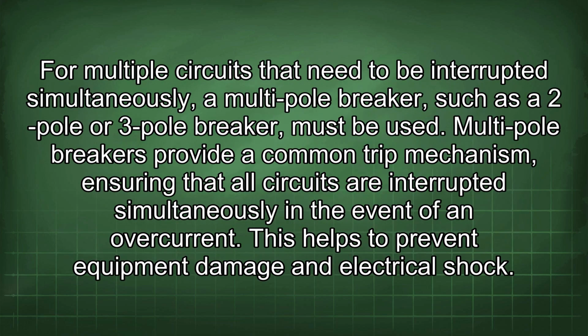For multiple circuits that need to be interrupted simultaneously, a multi-pole breaker, such as a two-pole or three-pole breaker, must be used. Multi-pole breakers provide a common trip mechanism, ensuring that all circuits are interrupted simultaneously in the event of an overcurrent. This helps to prevent equipment damage and electrical shock.